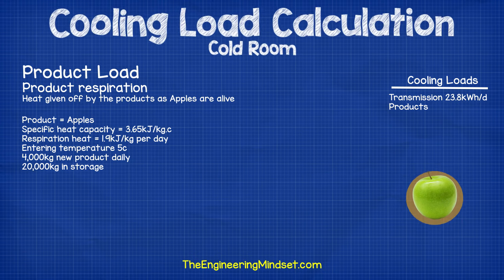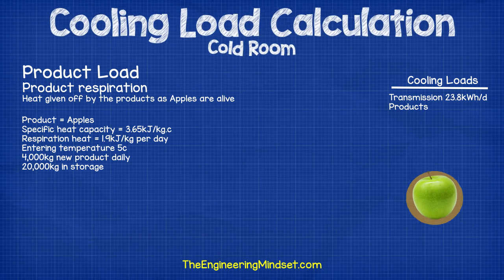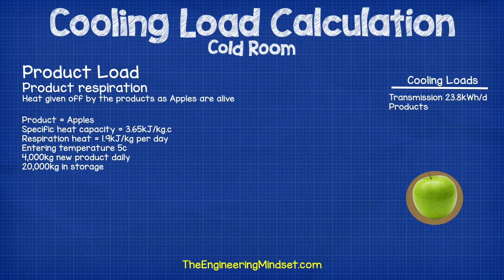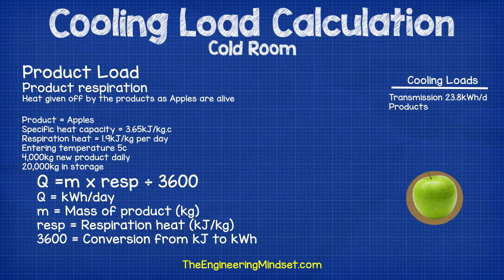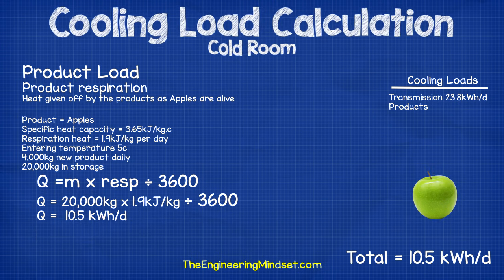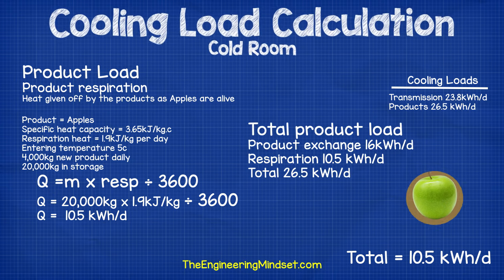Next we calculate the product respiration — the heat generated by living products such as fruit and vegetables. These generate heat because they are still alive; that's why we cool them down to slow their deterioration. For this example I've used 1.9 kilojoules per kilogram per day as an average, though this rate changes over time and with temperature. Using the formula q equals m multiplied by resp divided by 3600, where resp equals the respiration heat of the product, this comes out at 10.5 kilowatt hours per day. Summing the product exchange and respiration load gives a total product load of 26.5 kilowatt hours per day.